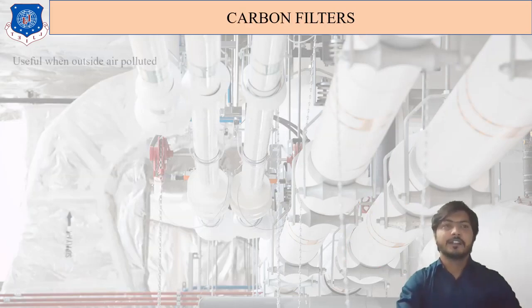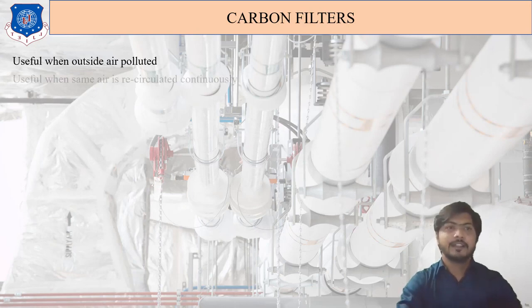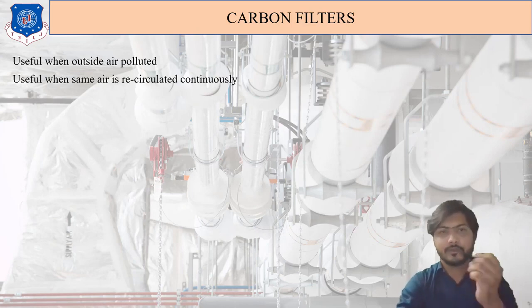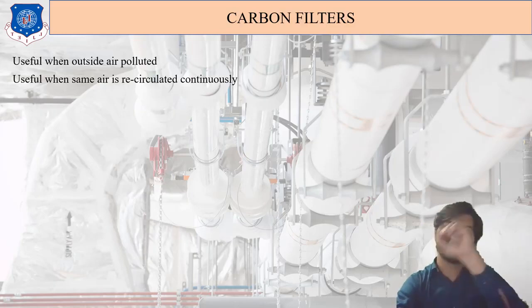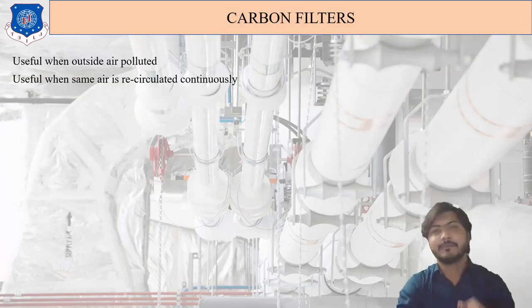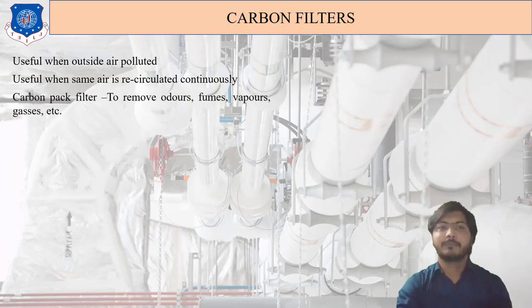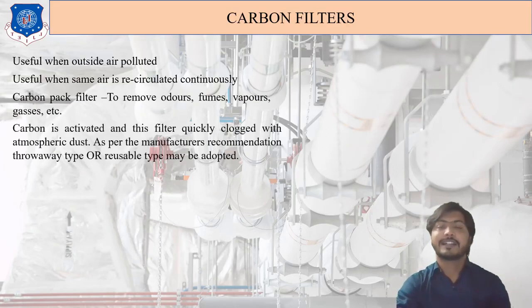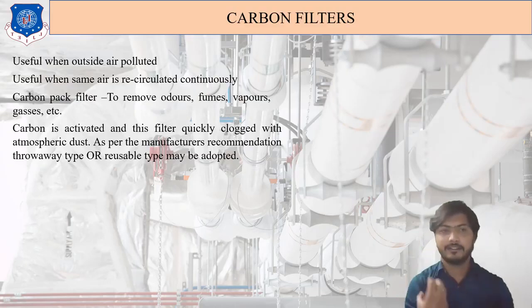Next is the carbon filter. What is a carbon filter? It is useful when the outside air is polluted, and when the same air is recirculated again and again. At that time carbon filters are used. Carbon packed filters remove odors, fumes, vapors, gases, etc. The carbon is activated type, and these filters are quickly clogged with atmospheric dust. As per the manufacturer's recommendation, a throwaway type or reusable type may be used.